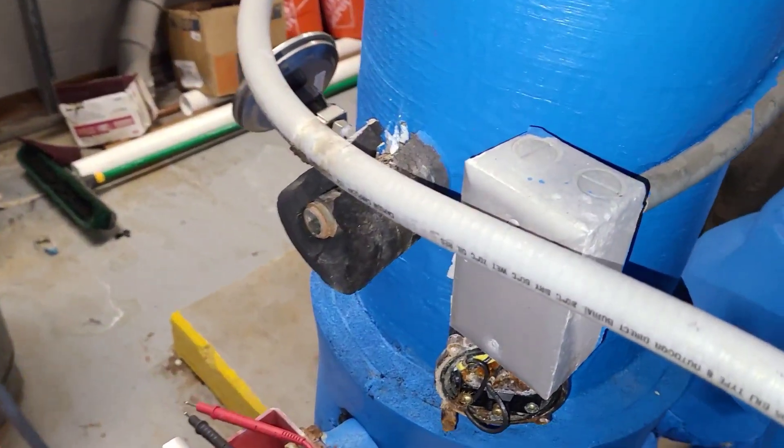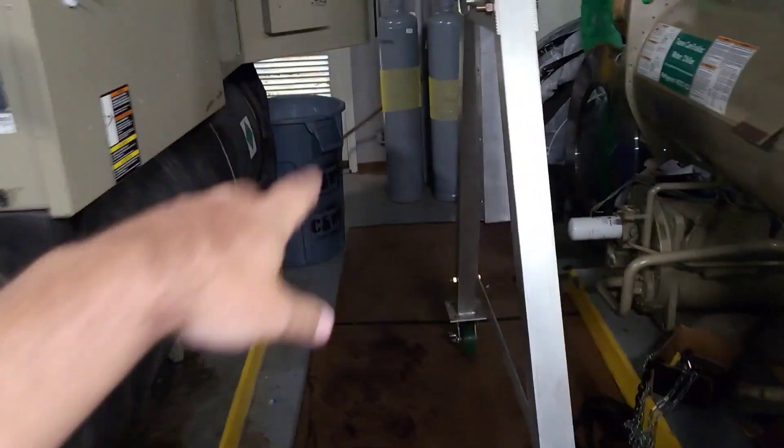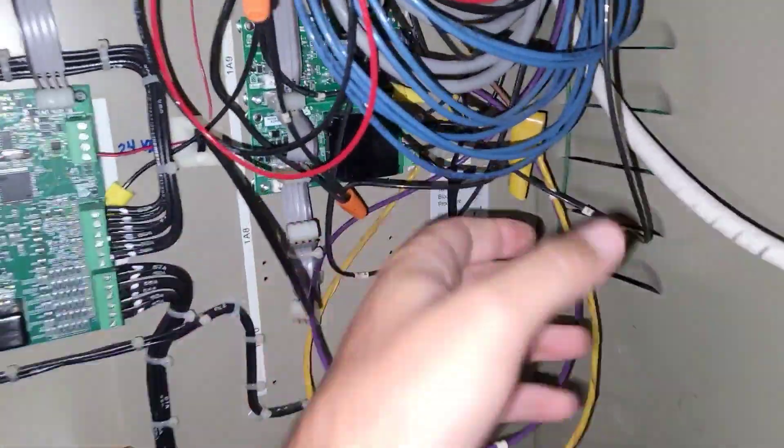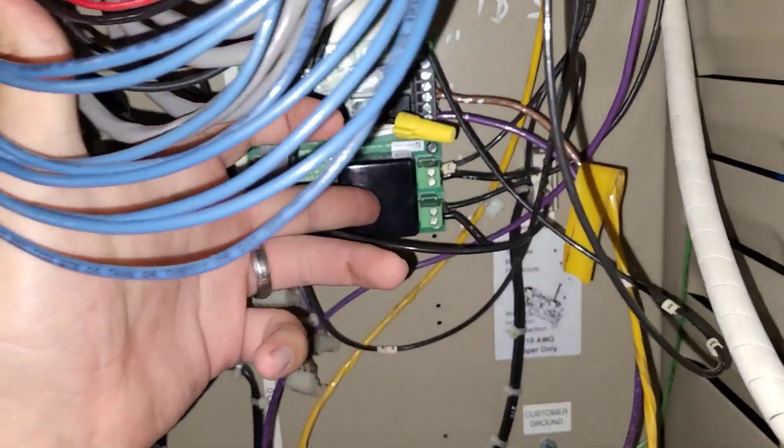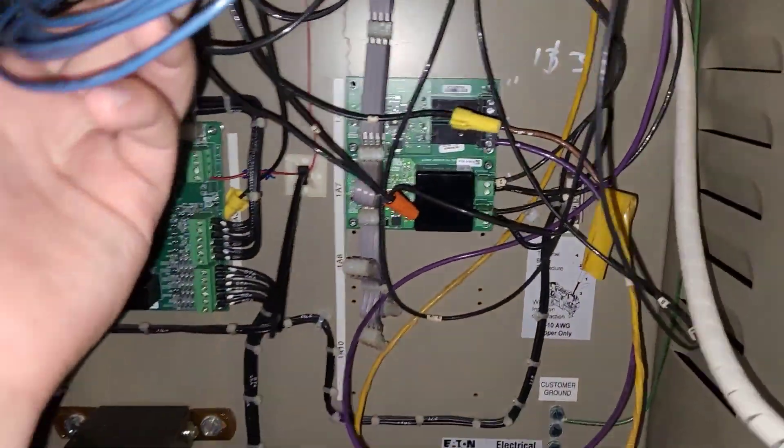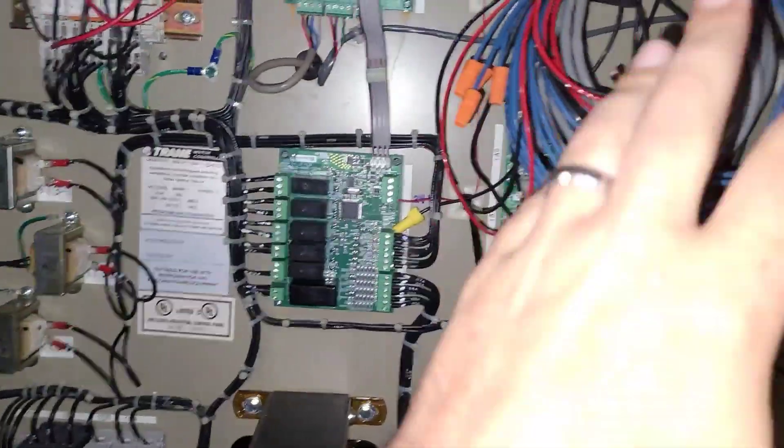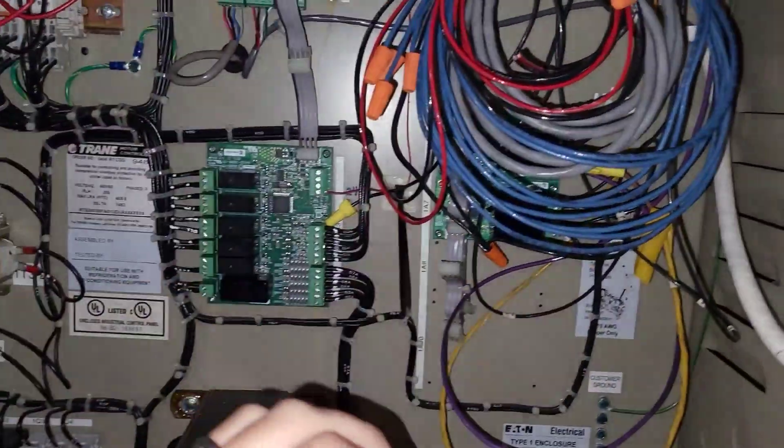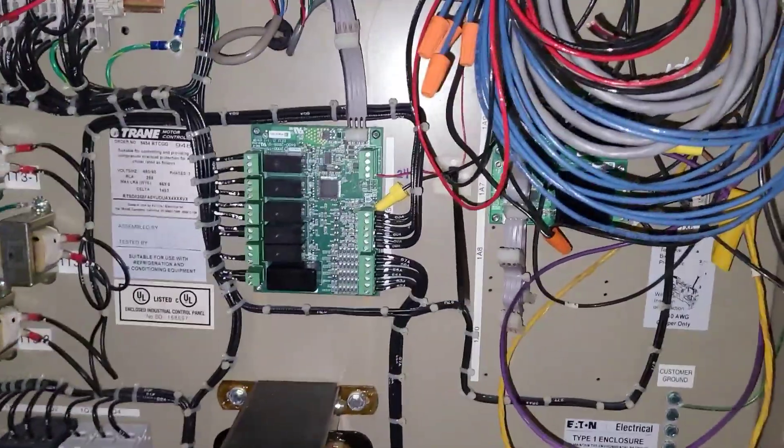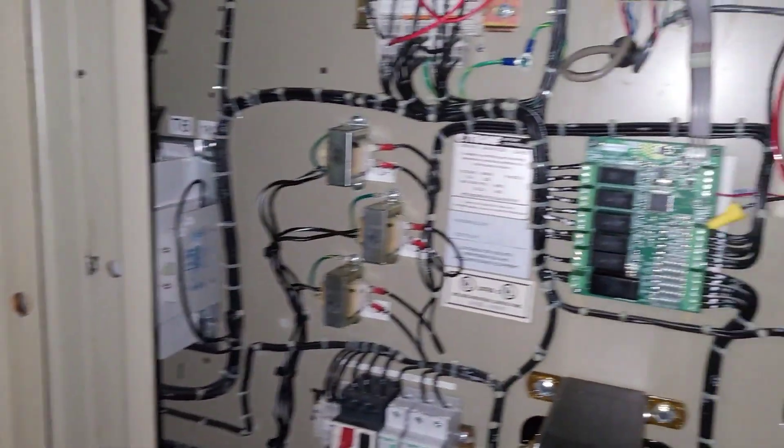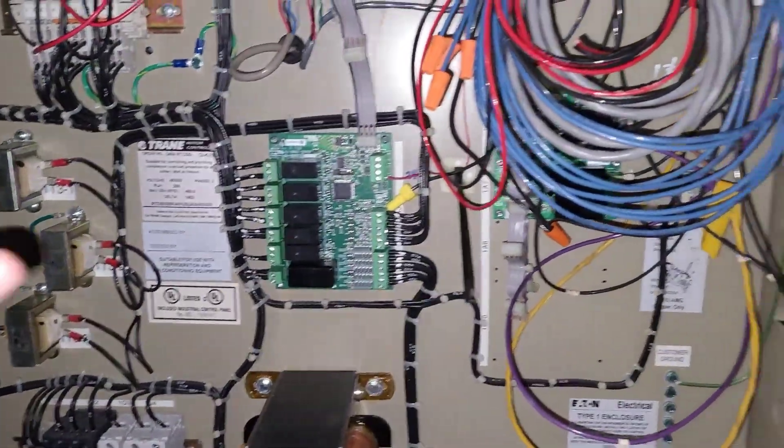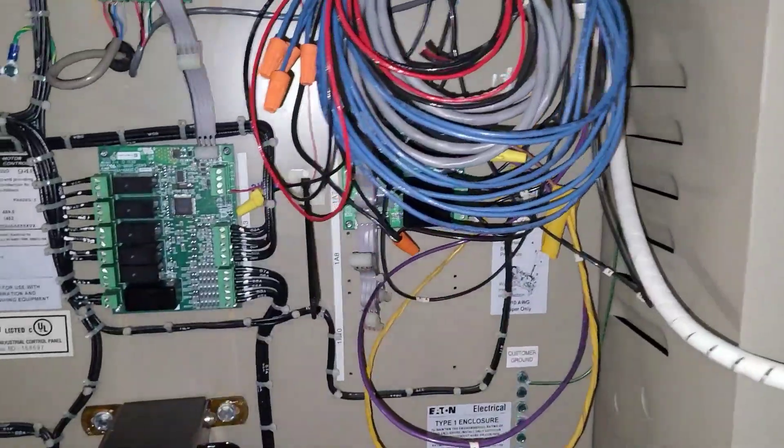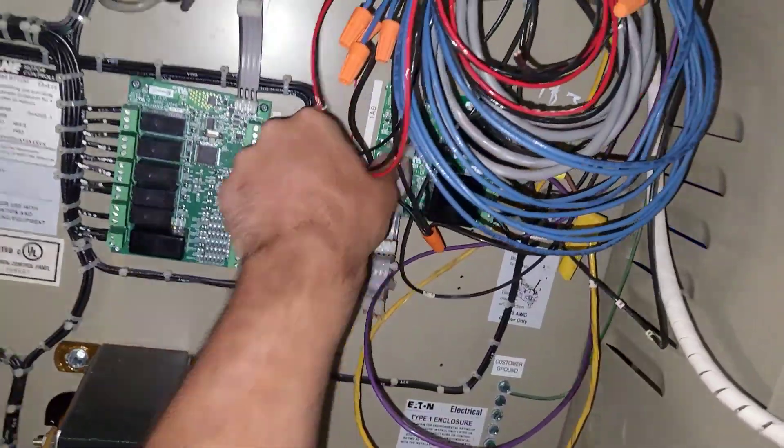I'll put this back together, and once I confirm which one of these it is here, I'll pull the wires. I'm pretty sure it's this card right here, fairly confident. 187, if memory serves. Anyway, we'll pull the wires off, we'll check continuity here at the control module. If it checks good at the module, that we've got continuity through the flow switch with it hooked up properly, then this is going to be our problem—one of our brand new cards we just put in here.